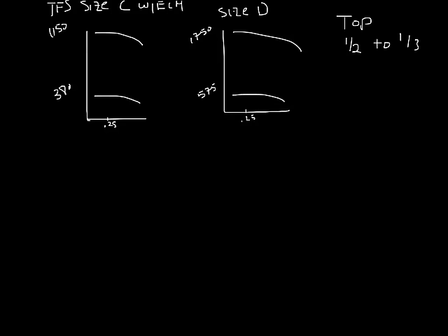It's best to select in the top half to third of a fan curve, because as you turn down the box, the motor will become less efficient. My example is an ECM motor, so it stays pretty efficient throughout the entire operating range, but it still will become less efficient as you turn it down.